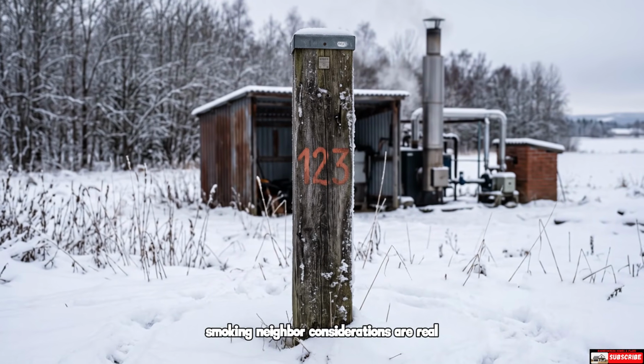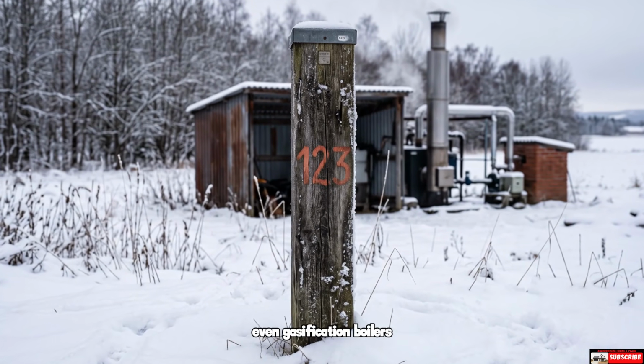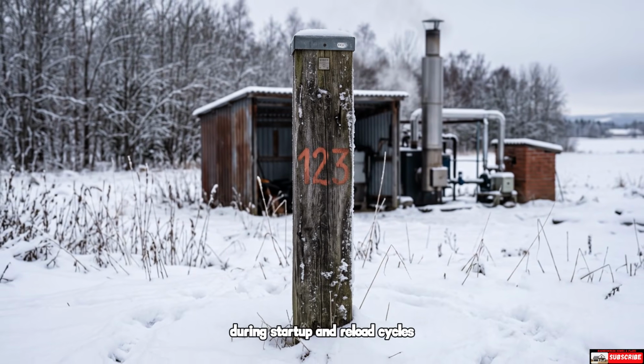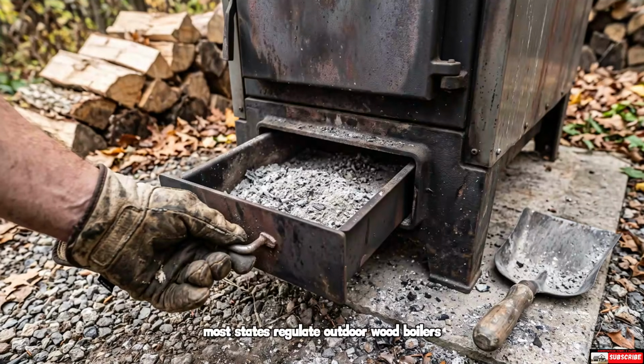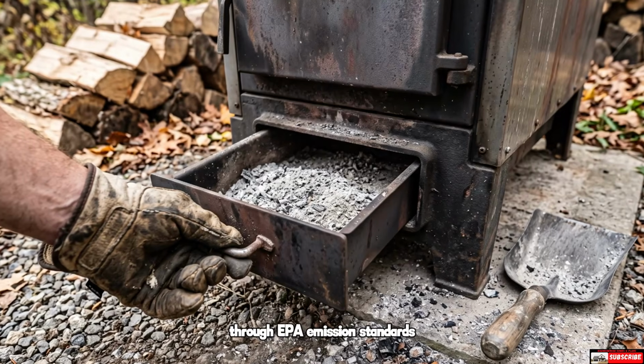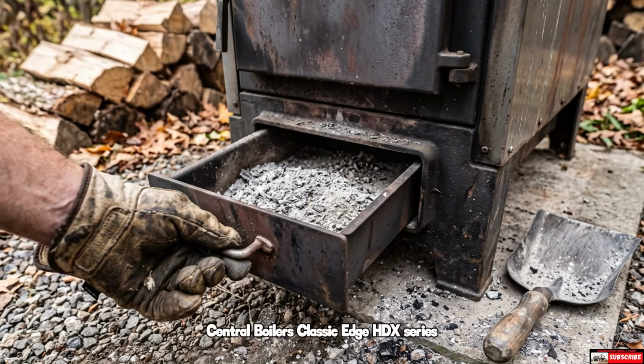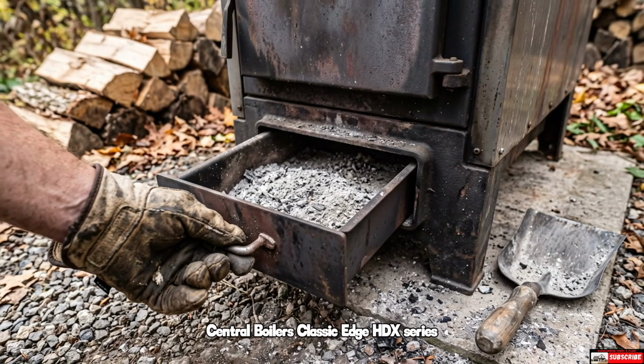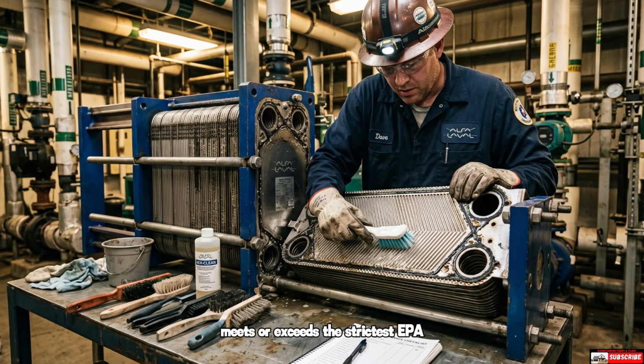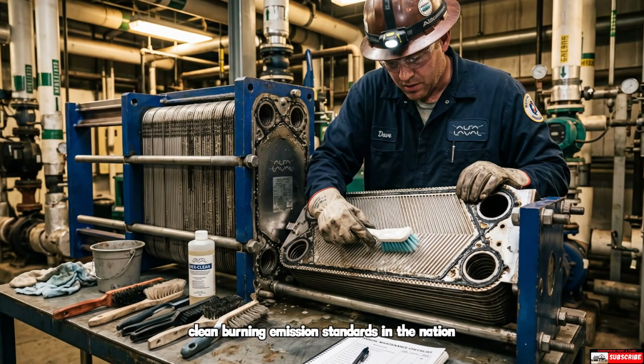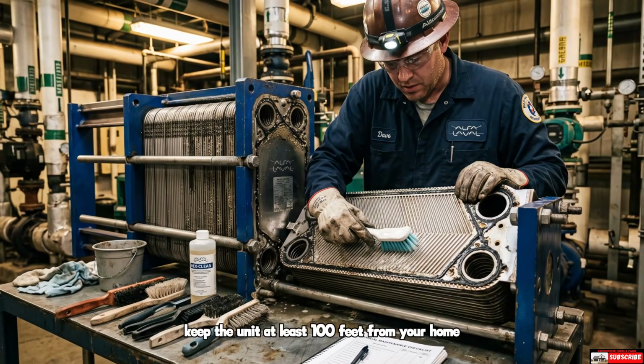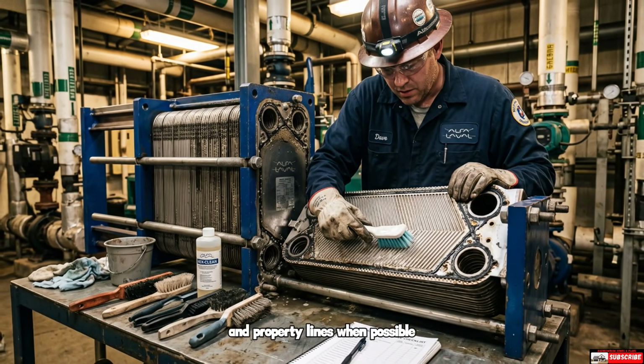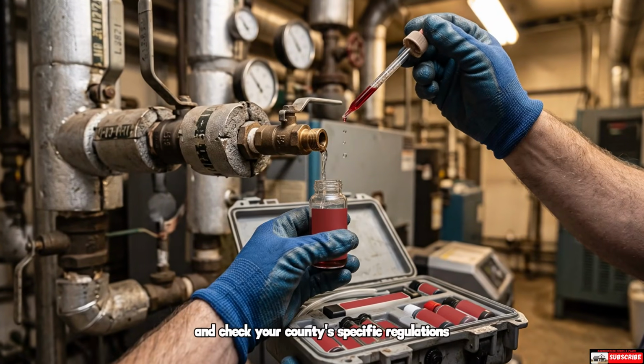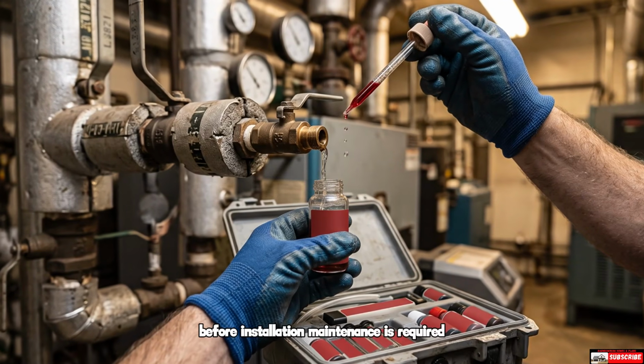Smoke and neighbor considerations are real. Even gasification boilers produce some visible smoke during startup and reload cycles. Most states regulate outdoor wood boilers through EPA emission standards. Central Boiler's Classic Edge HDX series meets or exceeds the strictest EPA clean burning emission standards in the nation, but placement matters. Keep the unit at least 100 feet from your home and property lines when possible, and check your county's specific regulations before installation.